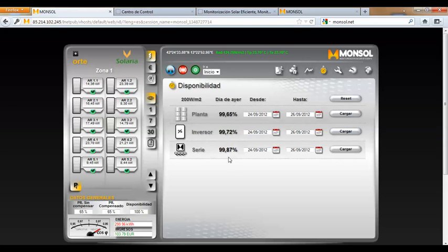This is how we calculate the availability. We suppose that 200 watts per square meter is the threshold value. With this amount of radiation, all components must be working 100%. Should there be a component that is not working for more than 10 or 15 minutes, this value is configurable, the system generates an alert. This alert takes away a certain amount of photovoltaic time of the corresponding component.